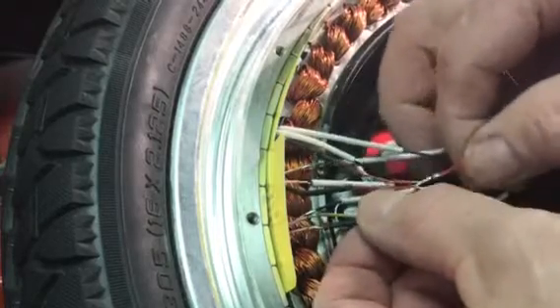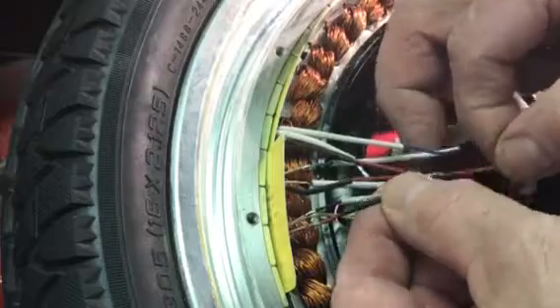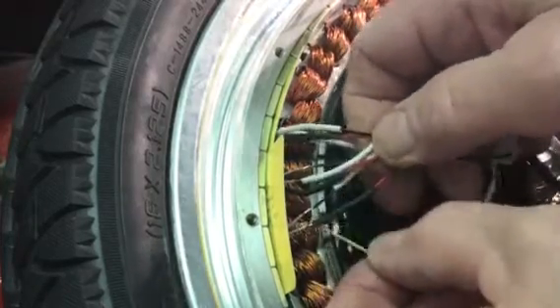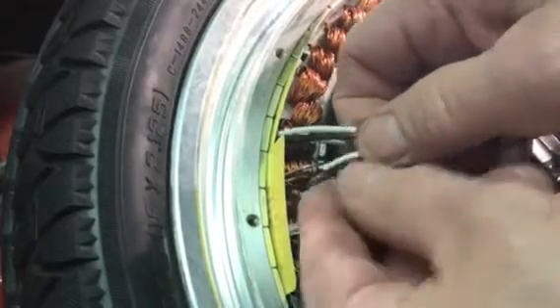This is a little bit concerning that I found around the hall sensors. Whoever slid these coverings over did not shrink wrap the wires, so all of these wires — if this little sleeve or sheath comes loose — are going to be exposed.